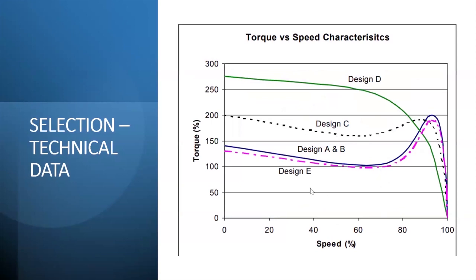According to NEMA design, we have the 5 design types, the design type A, B, C, D, and E. So based on your application, the motor behaves differently according to their torque. Let's look at a design class D. For a design class D, it has a very high starting torque, but as the motor approaches its full load speed, the torque reduces. So if you have a load which has dynamic torque, which torque increases with time, like with a crusher application, and you select a design class D, though it can start it all right, but in the course of running, you'll be having a lot of trips. The motor will trip. Maybe you need a 400 kilowatts motor or a 280 kilowatts motor. But with a design class D, it will not be able to accommodate the torque.